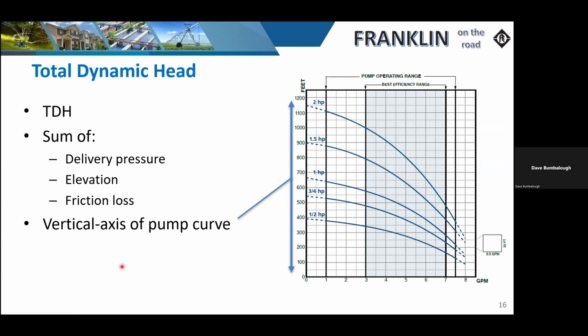So the whole purpose of this curve is to kind of give you an idea, what are we looking at here? I prefer the curves here. They give me a better idea of what's going on. Most manufacturers will tell you exactly where that pump range is able to operate in. So a 5 gallon per minute pump, it shows here that it will successfully go down as far as 1 gallon per minute and as high as about 7.5 gallons per minute on this particular design.